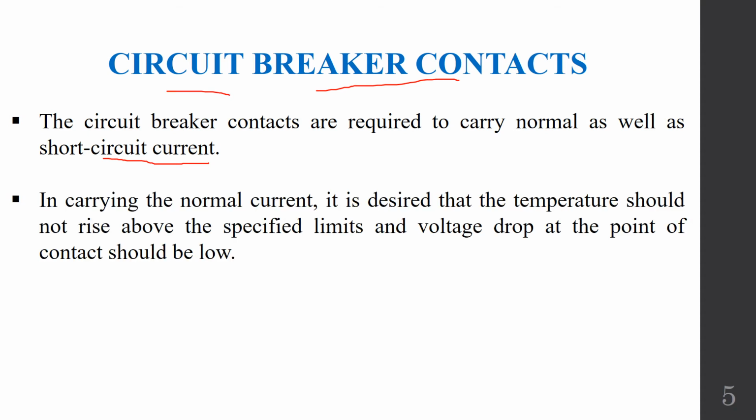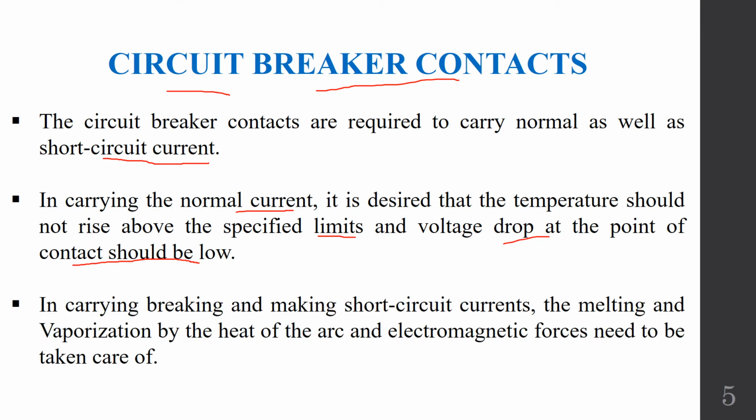Thus, during the normal operation, when the circuit breaker is carrying the normal current, it is desired that the temperature should not rise above the specified limit, plus the voltage drop across the contacts should also be low. In the same way, when the circuit breaker is carrying the breaking or making short circuit current, then the melting and the vaporization by the heat of the arc so formed between the contacts when they are separated, and the electromagnetic force build up need to be taken care of.